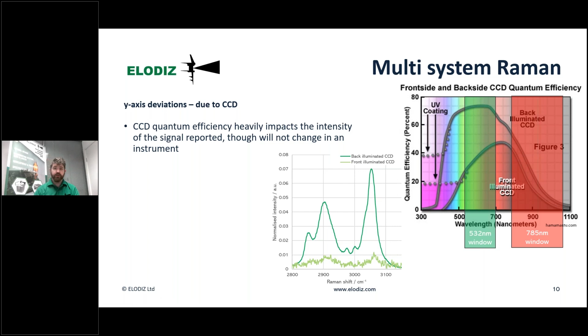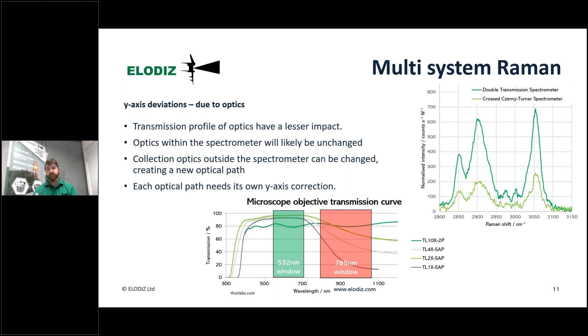Another large factor is the spectrometer's optics, as well as the optics used for collecting your information. At the bottom, you can see the transmission curves and how they differ for the same manufacturer, same type of microscope objective, but using ones that have different magnification values. So these can obviously impact the result of your data. That tells you that for each optical path, you need to have individual y-axis correction, even if all you're doing is changing the turret and changing a microscope objective from one to another. The graph over here is showing again that CH region, and it's showing the behavior of the different optical setups within the spectrometer, either cross CT or double transmission, and the way in which that can affect the resulting data.